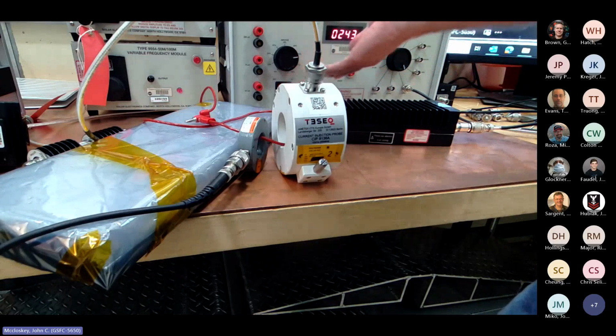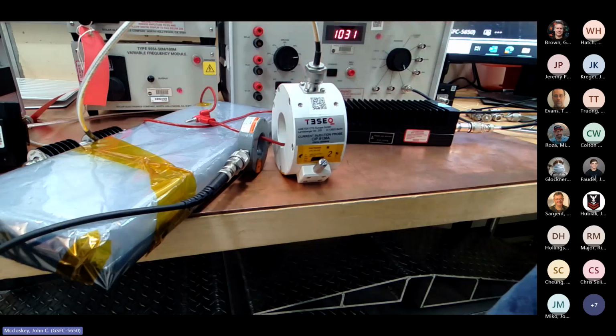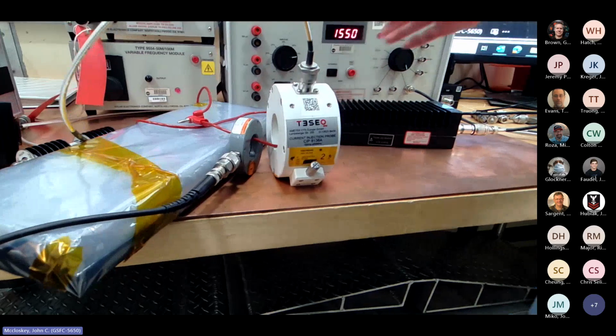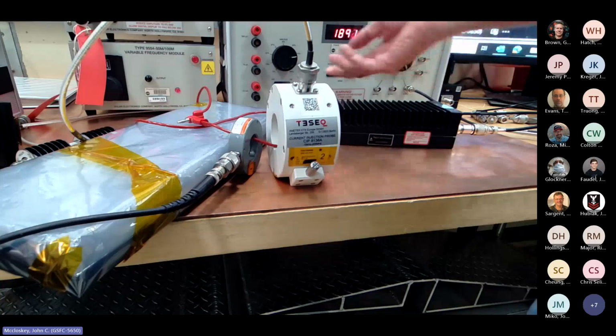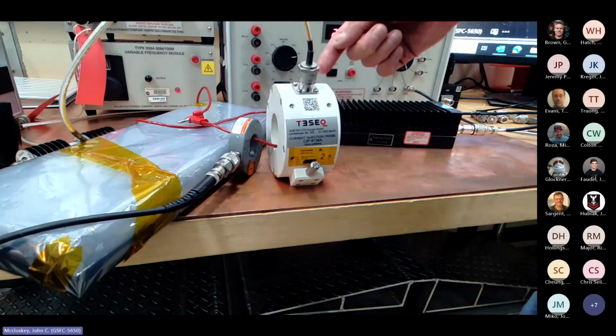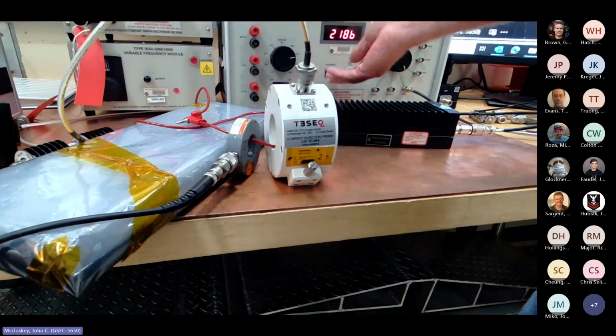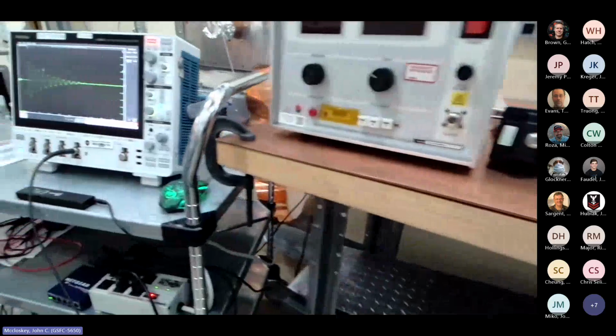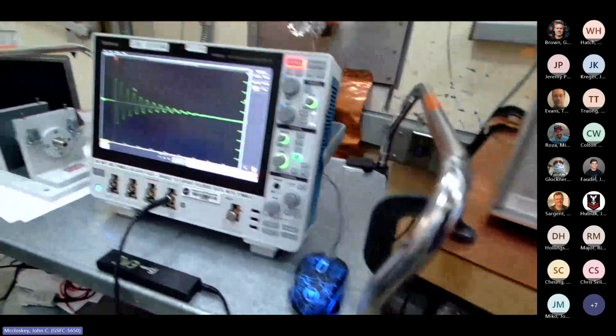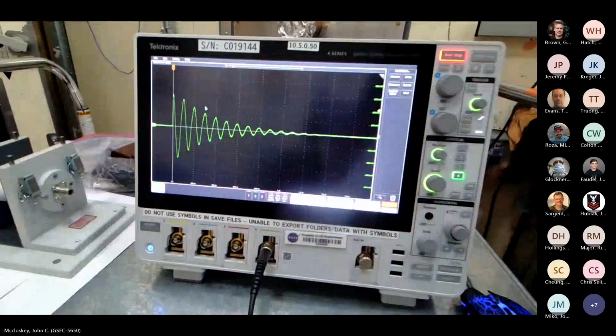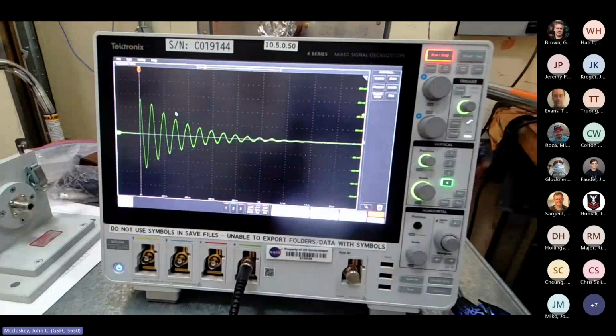So we'll turn the signal generator on. Everything should be the same as what we just left it for. We're still set for 10 megahertz, with the drive amplitude to give us 1 amp into our cal fixture. Now turn the generator back on. That's our calibrated signal.